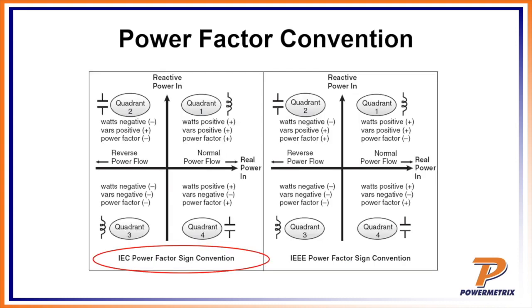Okay, now if four quadrant metering wasn't as complex as it is, now you guys get to deal with power factor. I just learned this maybe a few months ago - there are actually two different conventions, two different styles of power factor when it comes to four quadrant metering. There's IEC and there's IEEE. IEC is commonly used in European countries, and IEEE is mostly used in North American countries. Ironically, most of the industry follows the IEC concept, and so do we. Powermetrix follows the IEC concept. I've discovered, though, that one particular meter manufacturer - I won't say which one - follows IEEE. Why is that a problem? Because it could result in totally wrong metering, you'll see here in a second.